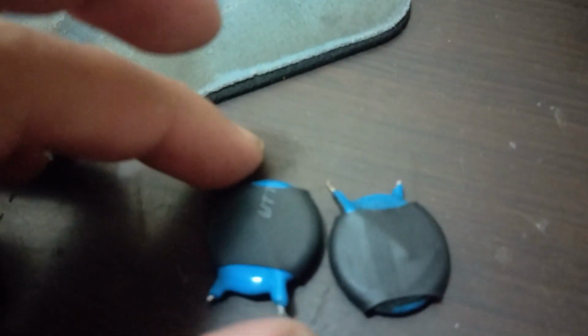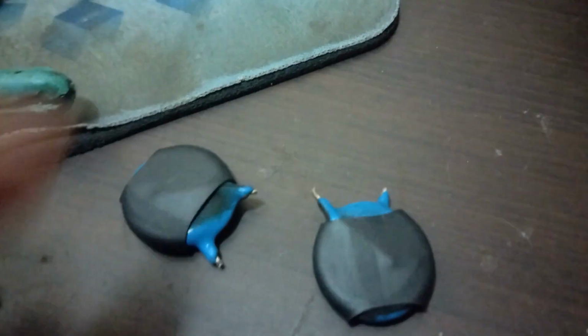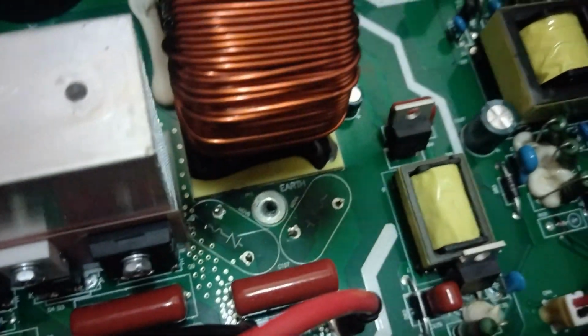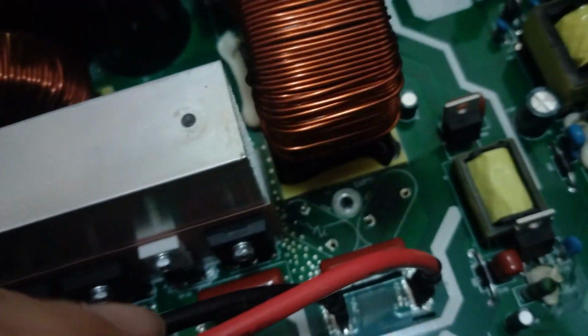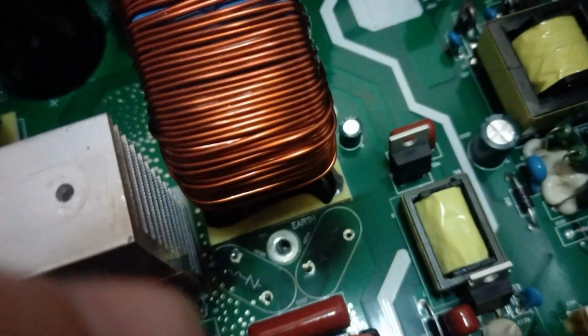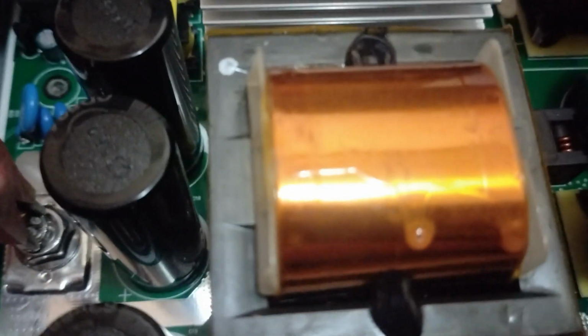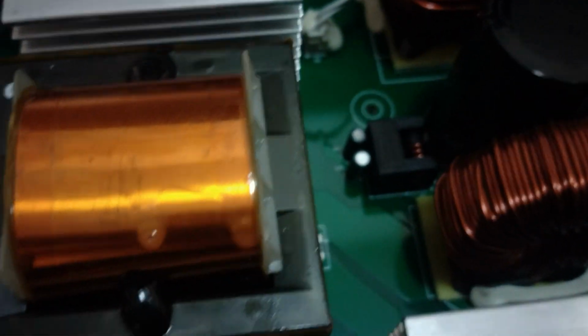And we found the culprits, these MOVs, metal oxide varistors. These are designed to suppress any high voltage spikes. It's like a surge protector, and both of them have gone completely short circuit and split open. And they are on the solar input, so I'm guessing the solar got struck by lightning. Shorted those out, which took out those, and it took out one from each side of the MOSFETs for the 48 to 380 volt supply.